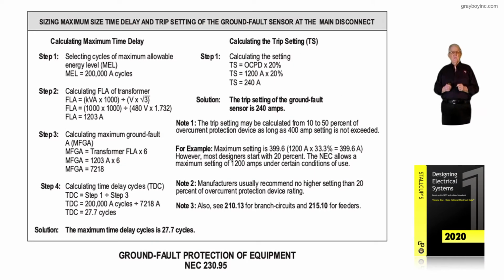Now, this illustration deals with ground fault protection of equipment in accordance with 230.95, which is service. But notice in note 3, we are talking about a branch circuit in 210.13 as mentioned, and for a feeder 215.10.